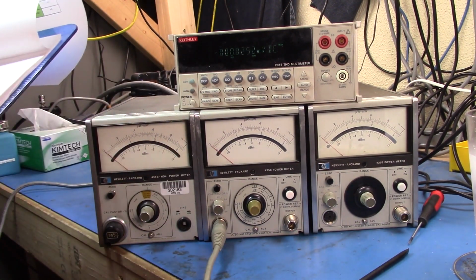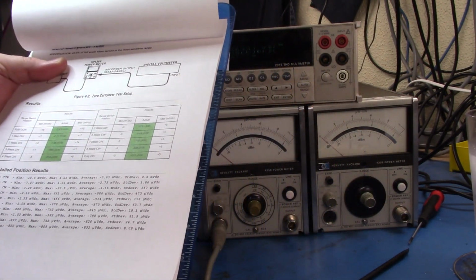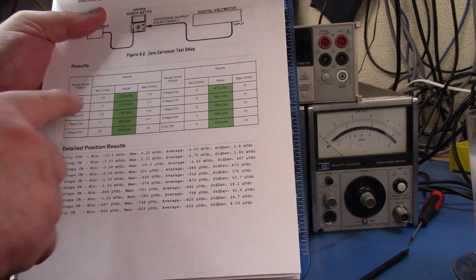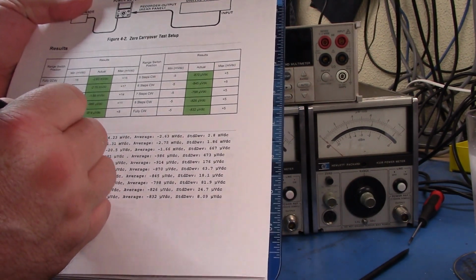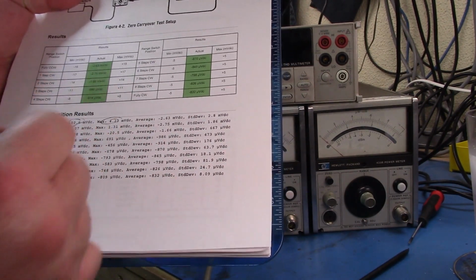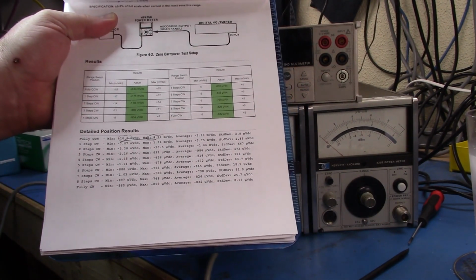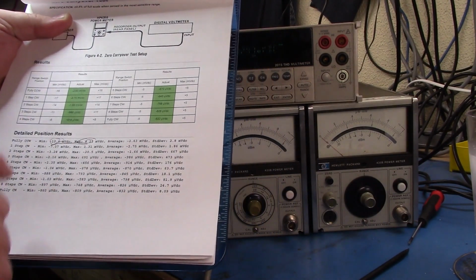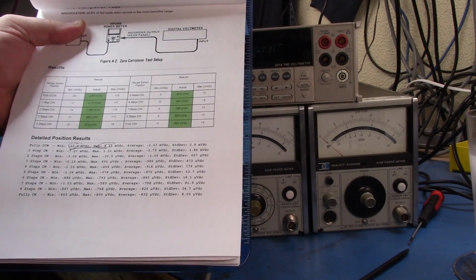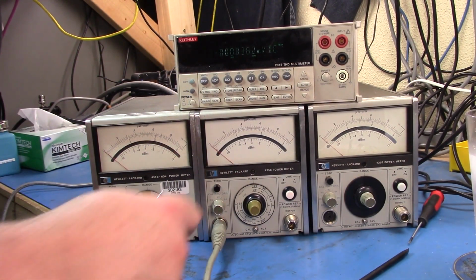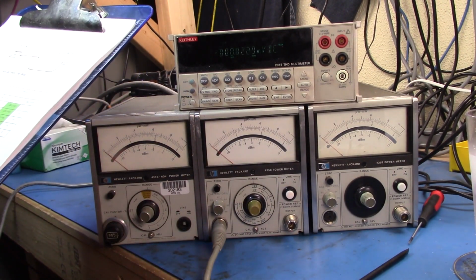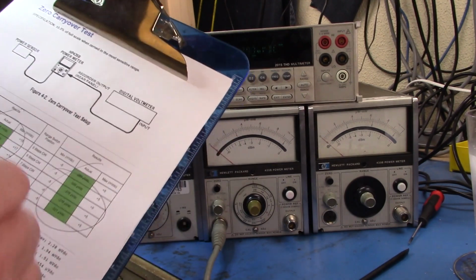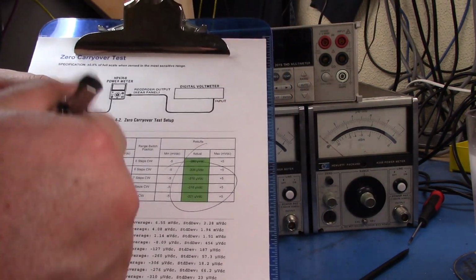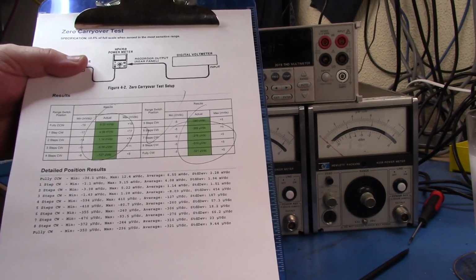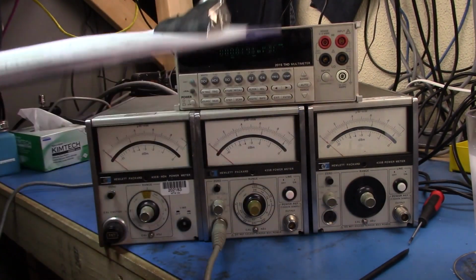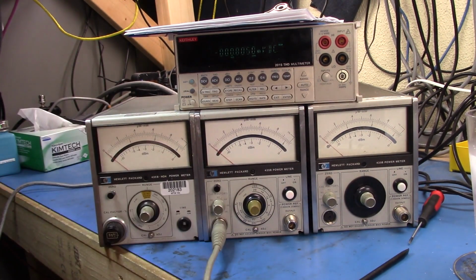This was the one that I was having a bit of an issue with in terms of the noise that was involved in it. If you look, it's also passed, but it has quite a bit of noise range there between the mins and maxes. It is still within the results, but it is way noisier than this meter here. So at least what we're seeing is that these values are in fact a pass. That is telling me that the meter's good to move on to the next step, which is to look at the range accuracy.